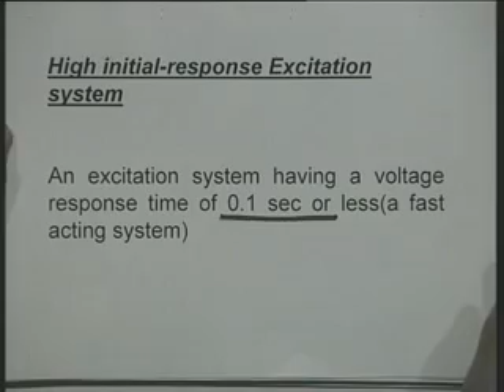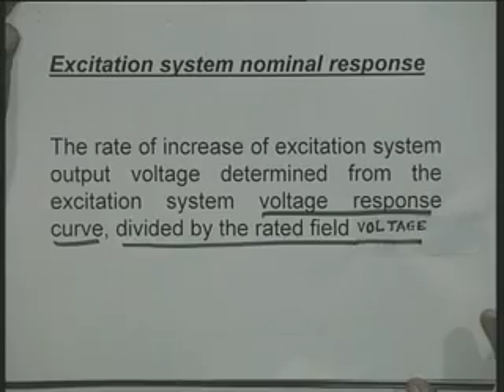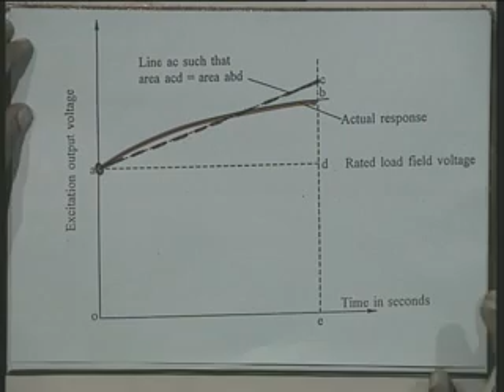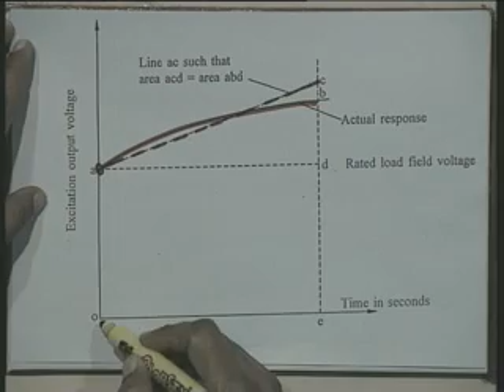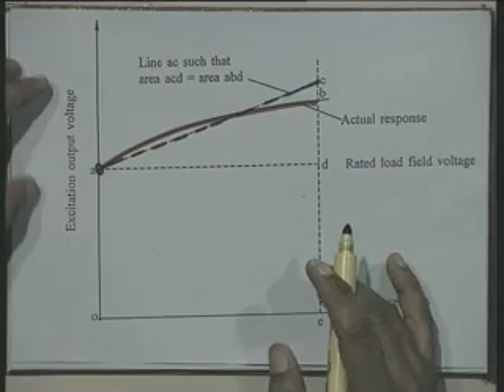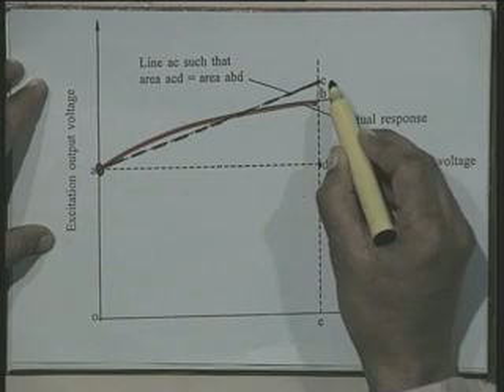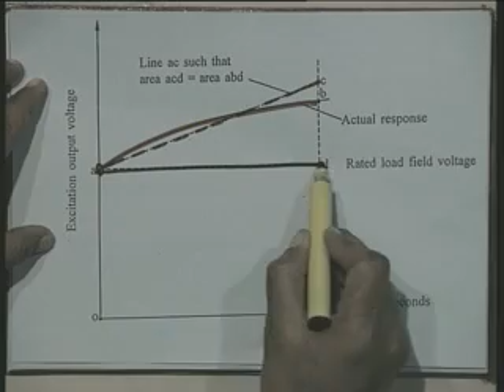Then we also define a term which is called the excitation system nominal response. To understand this, let us look at the voltage response of an excitation system. Here in this graph, the excitation system output voltage is represented by OA, and the terminal conditions are created so that the voltage increases and follows this curve. Then on this time axis we choose a time equal to 0.5 second, represented by the line AD. Then we draw a straight line passing through this point A in such a fashion that the area ABD is equal to the area of this triangle, ACD.